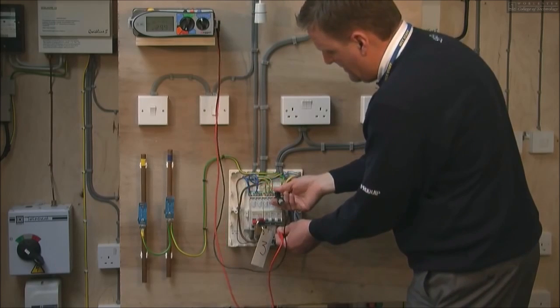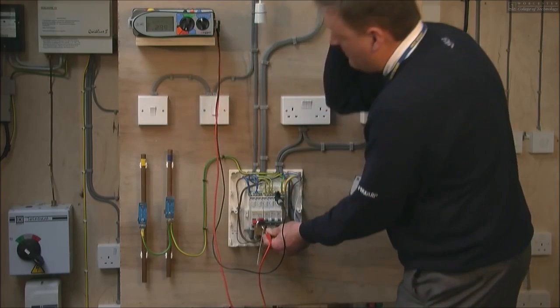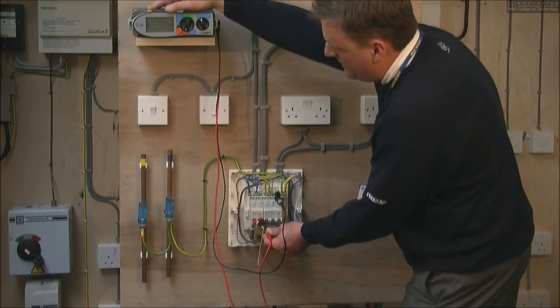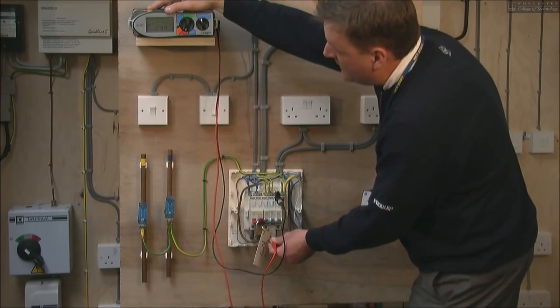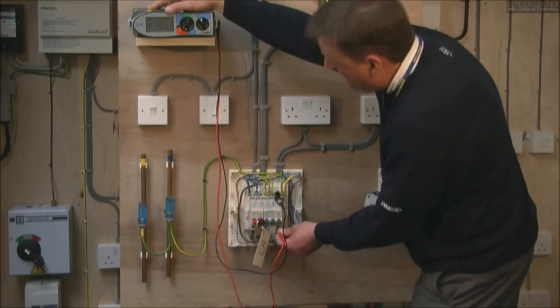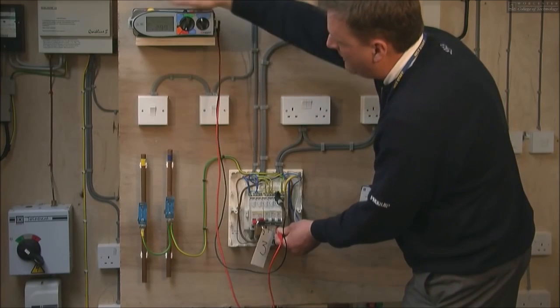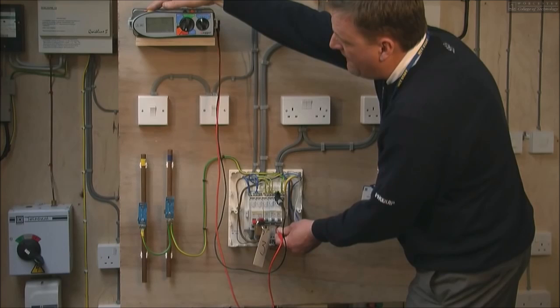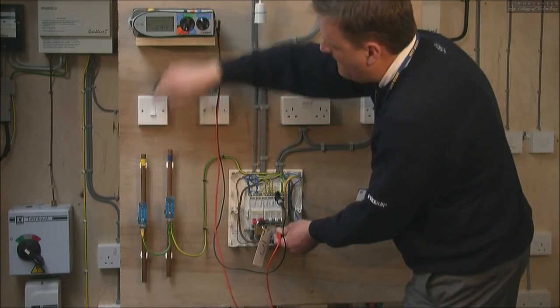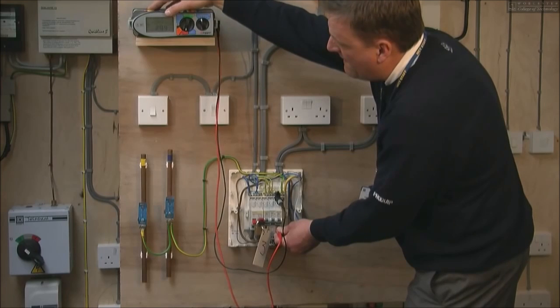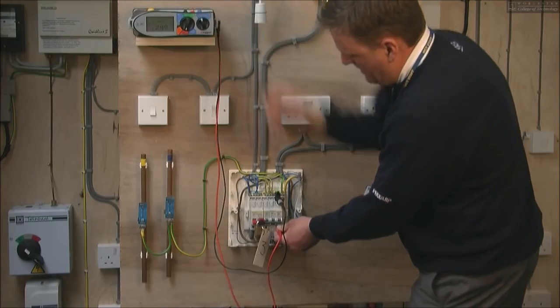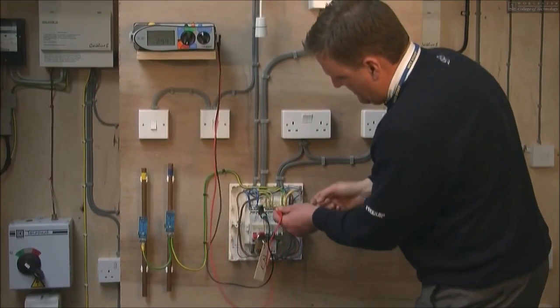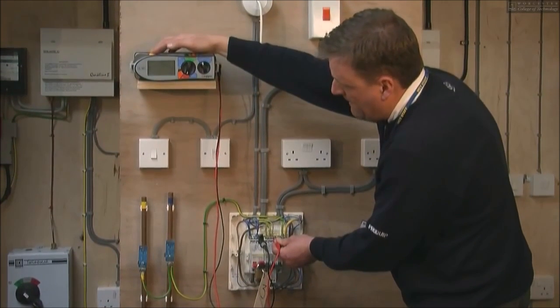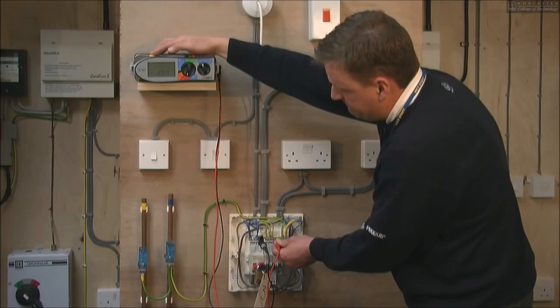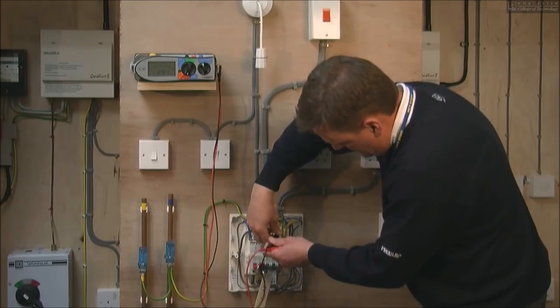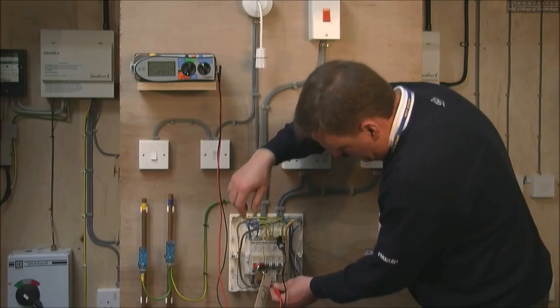We then clip onto the main earth terminal, and we work our way across again onto the line conductors. As you can see, there's no deflection. And again on the lighting circuit, like so. We then go from the neutral to earth, and remember that the RCD also has a separate neutral.